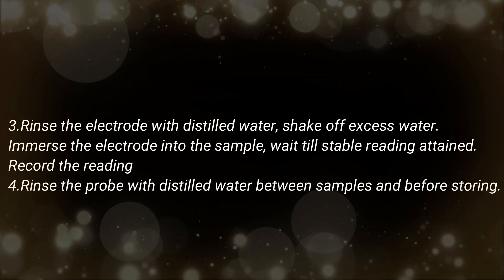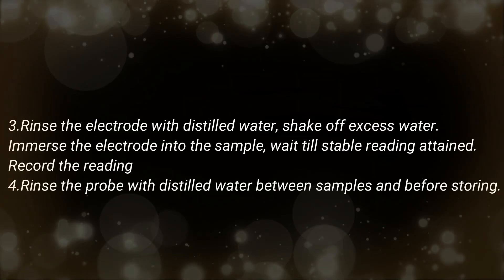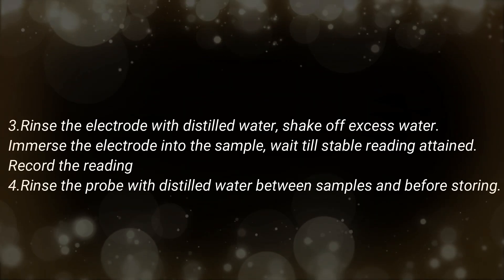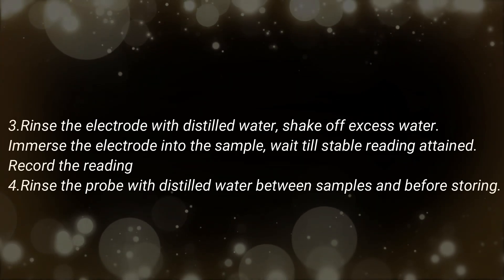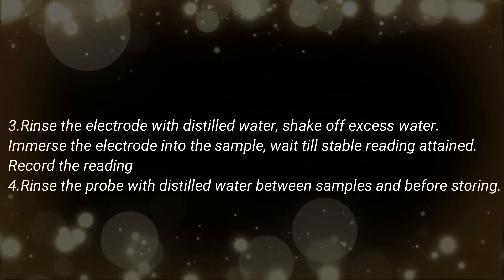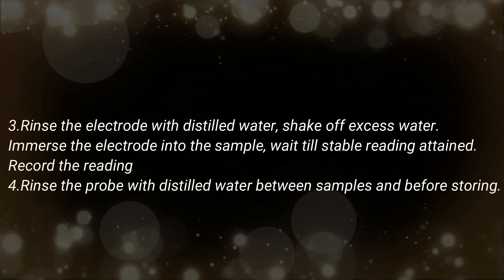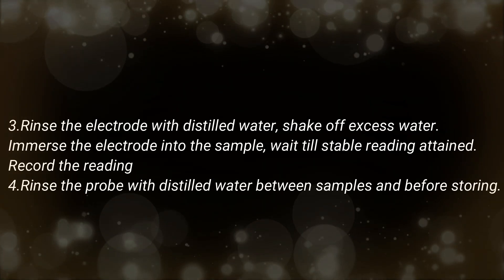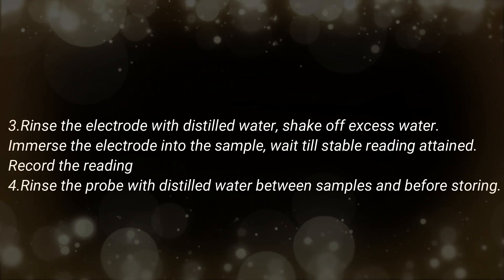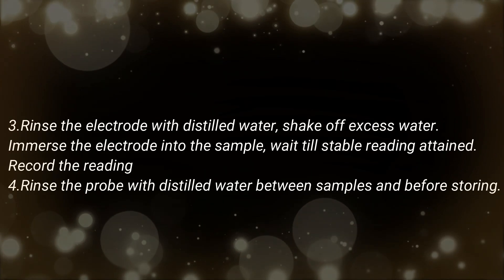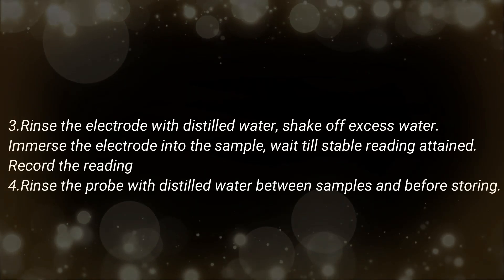Insert the electrode into the sample. Wait until a stable reading is obtained. Record the reading. Rinse the bulb with distilled water between samples and before storing.